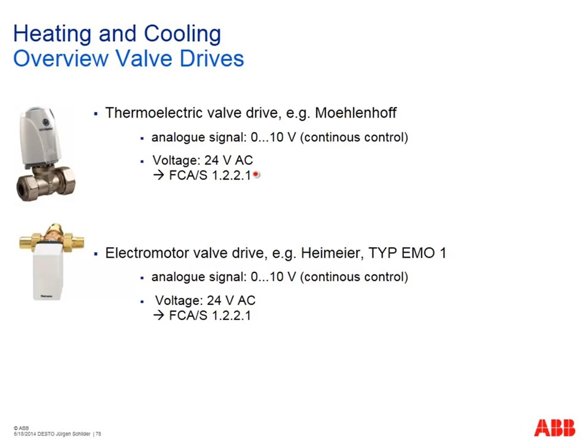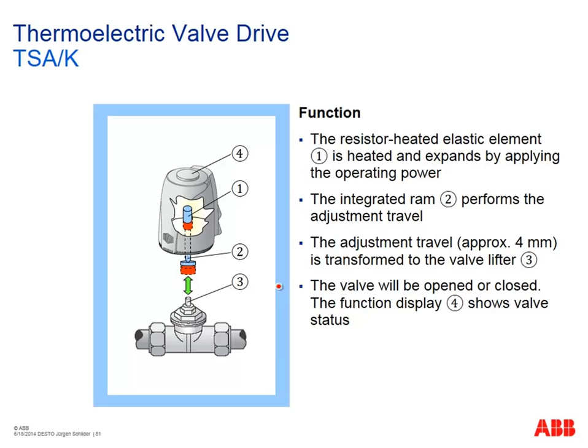And these electrothermal valve drives, only one slide to understand the principle of how it works. A very simple device, cost efficient, very reliable, let's say. The principle is that we need nothing else but an electrical circuit to control this. We close the contact to heat up an elastic element inside the device, which will expand in such a case, and then it will press on the valve behind. If it's a normally closed valve, then it will be opened by pressing down this pin. And if you open the contact, meaning you cool down the elastic element, it will shrink, and then it will release this pin again, and the water flow will be closed. It's a very simple device. We need nothing else but an electrical circuit, a contact behind, and the functions you have seen in the last slide are two-step control or pulse width modulation.